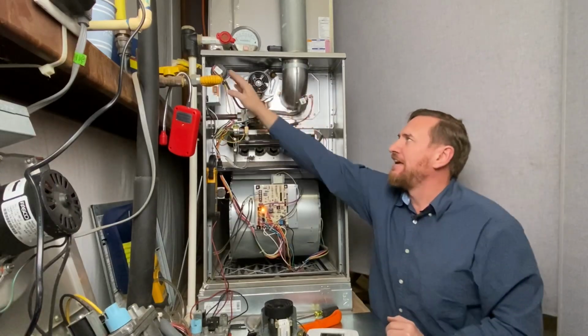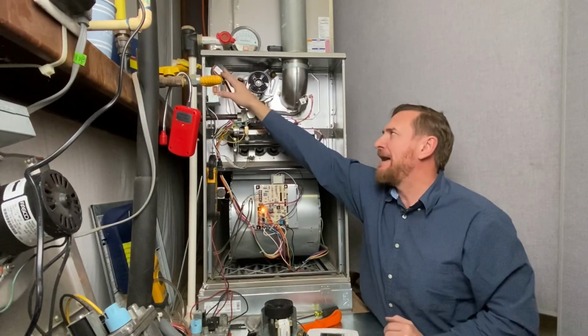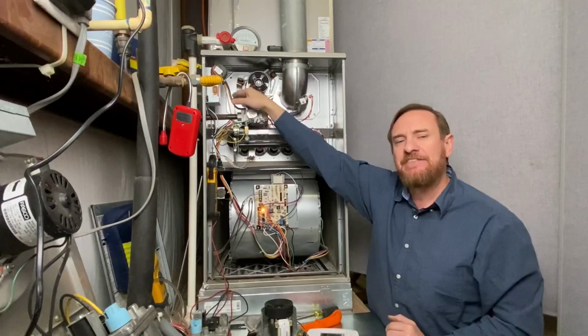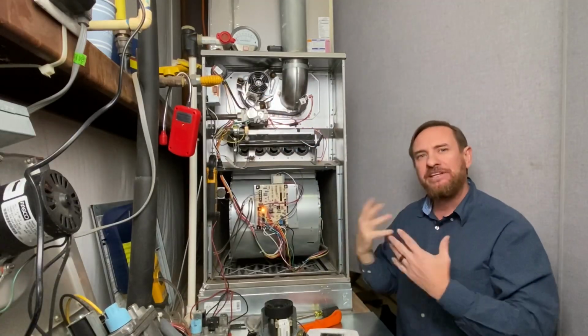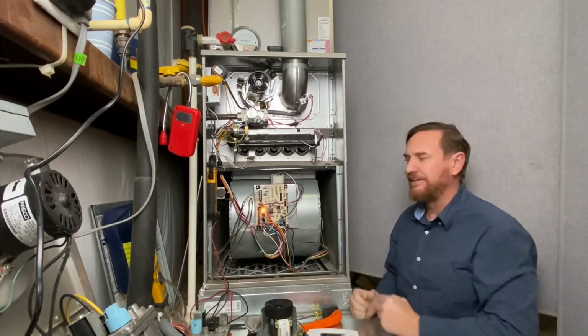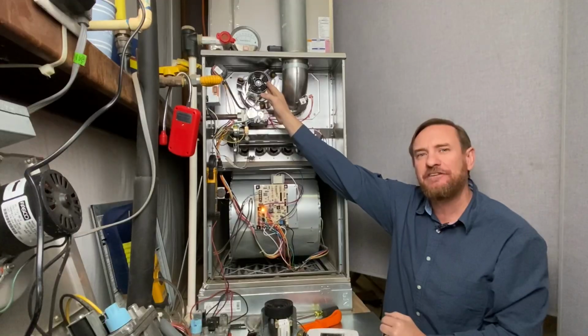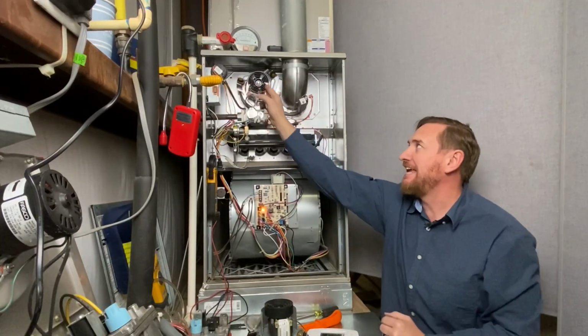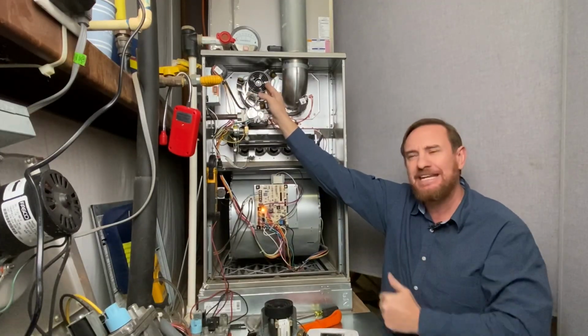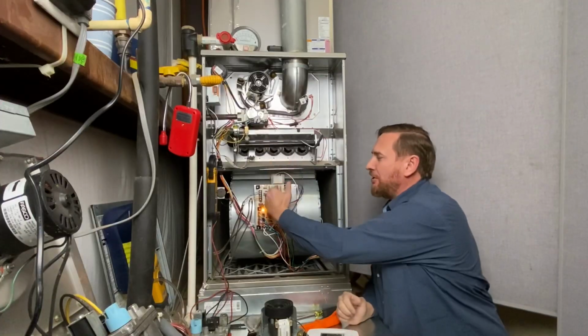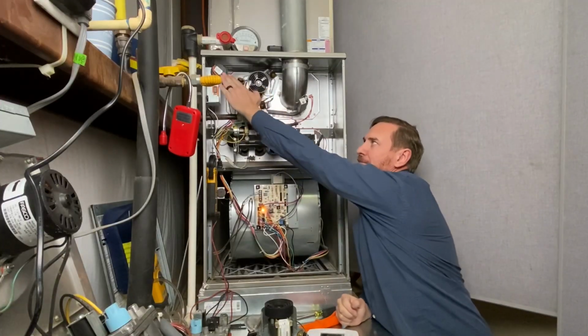So you don't just say, hey, this switch is not closing, it's bad. Let's make sure, is it getting the vacuum all the way to there? This is what you need to be thinking about. This is what the control board sees. It energizes this. It can't tell if it's working. This is the snitch saying, hey, this guy's doing his job. We're okay, keep going.